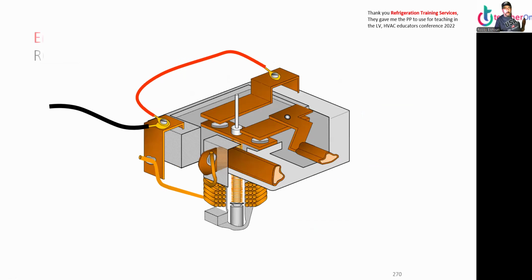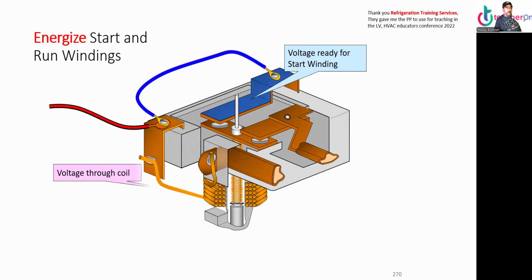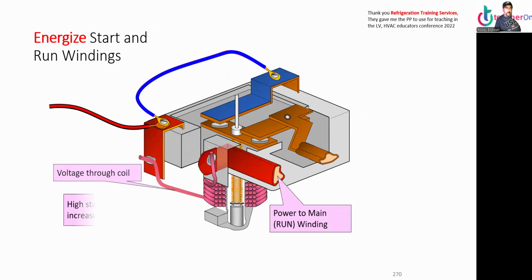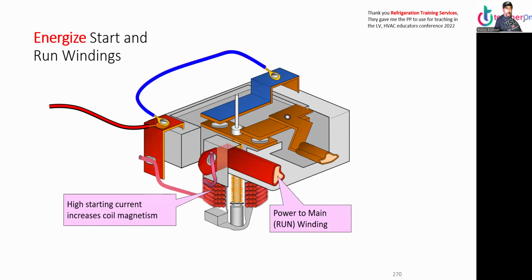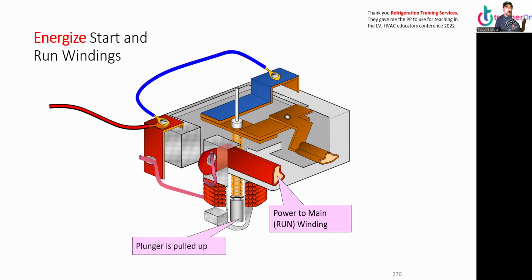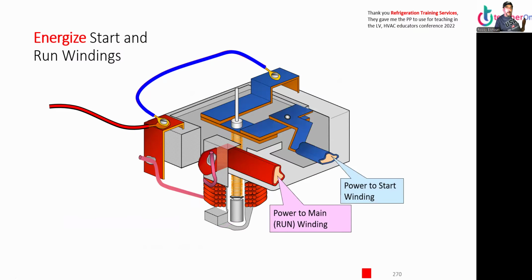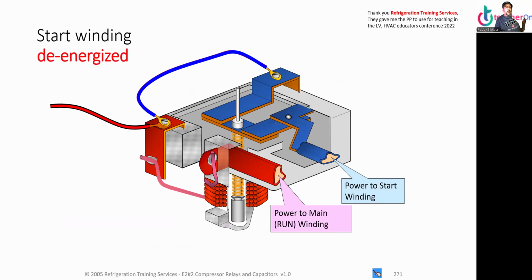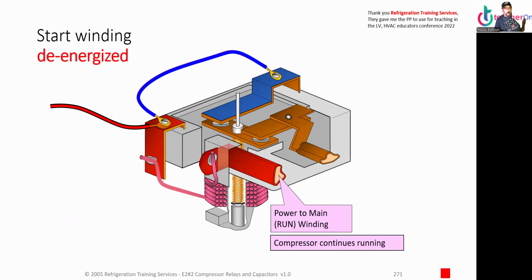And to start, energizes start and run windings, voltage through the coil, and out to the main run windings. High starting current increases coil magnetism. Plunger closes. Power to start winding. Now it will de-energize as motor speed increases, amperage falls, and it opens.